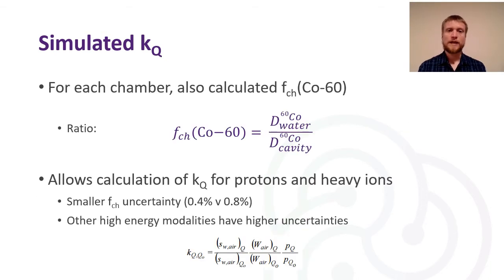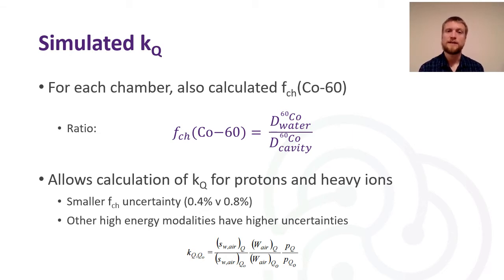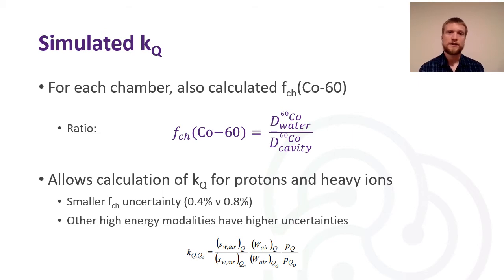For each chamber we've also calculated the FCH in Cobalt-60, which is essentially the denominator from the previous equation — the dose to water over the dose to cavity in Cobalt-60. This allows a more accurate calculation of KQ for protons and heavy ions, with a smaller uncertainty. This new consensus value has an uncertainty of 0.4% compared to 0.8% in TRS-398. It's also beneficial because a consistent set of FCH values is preferred over calculating stopping power ratios and perturbation corrections every single time, ensuring more consistency in those calculations.